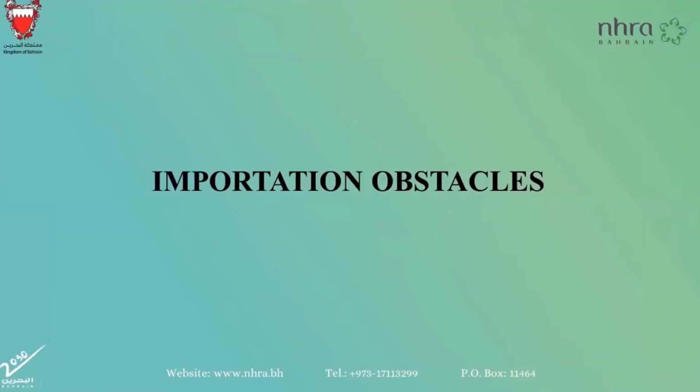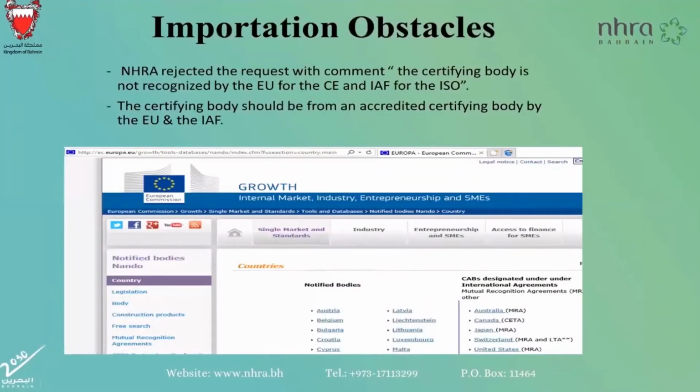Now I will talk about some importation obstacles. NHRA rejects the request with the comment that the certifying body is not recognized by the EU for the quality assurance certificate and IAF for the quality management system. The certifying body should be accredited by the EU or the IAF, so always make sure that your certificate is recognized and accredited.